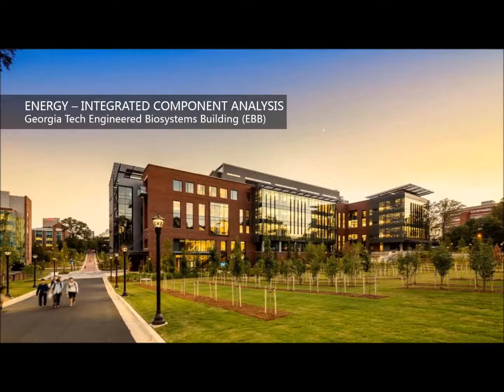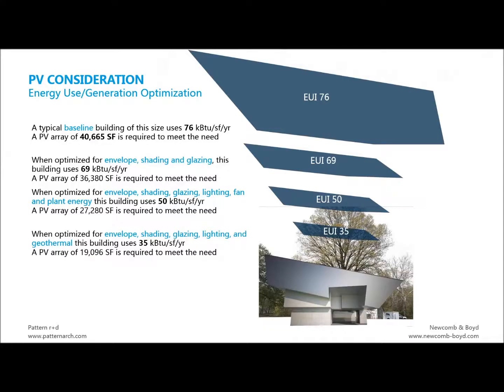In this case, on the east and west we do have shading. But on the south, for the lab areas, we found the solar gain was actually helping reduce the mechanical reheat needed in these high air-change spaces. So adding shading there was actually a detriment to overall energy use, and we went back and removed the shading from that side.